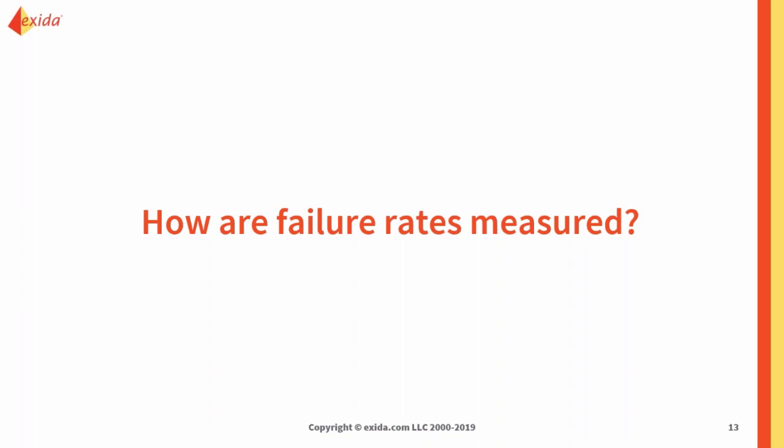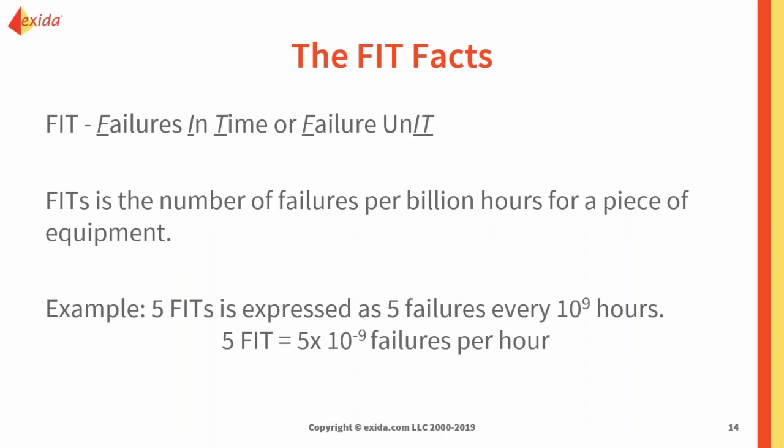So now let's look at how failure rates are measured. Well, failure rates are usually referred to as FITs, and FITs, depending on who you talk to, could be failures in time or failure units. And it's really the number of failures per billion hours for any piece of equipment. It's mentioned in both IEC 61508 and 61511 as the preferred unit of measurement. But always be careful and double check when you are talking about failure rates and make sure it is FITs, because every once in a while I've seen a failure rate expressed in 10 to the negative 6 instead of 10 to the negative 9. And it can get confusing.